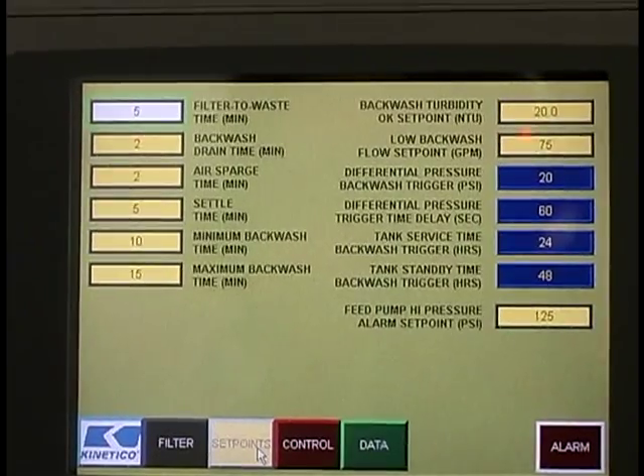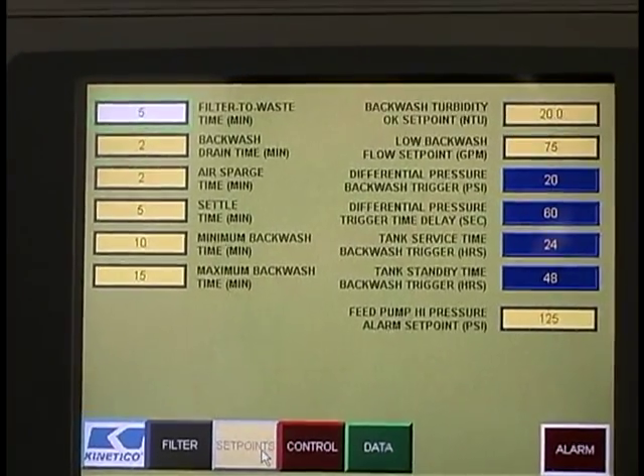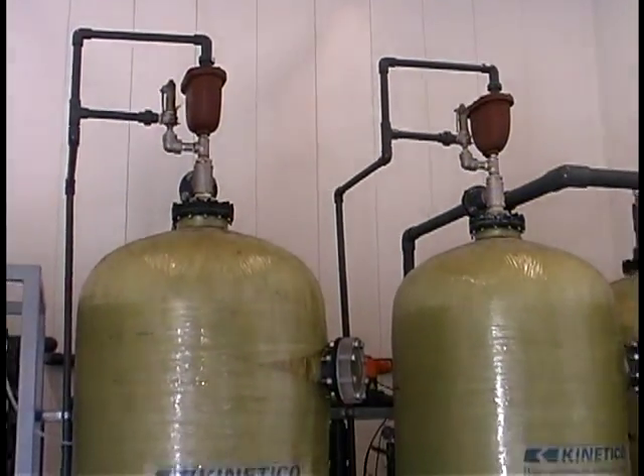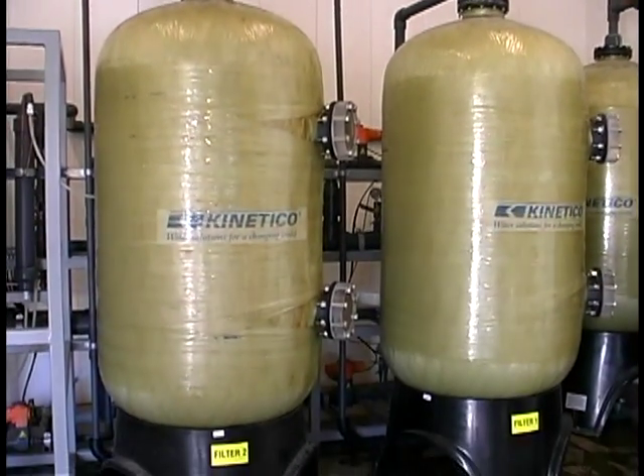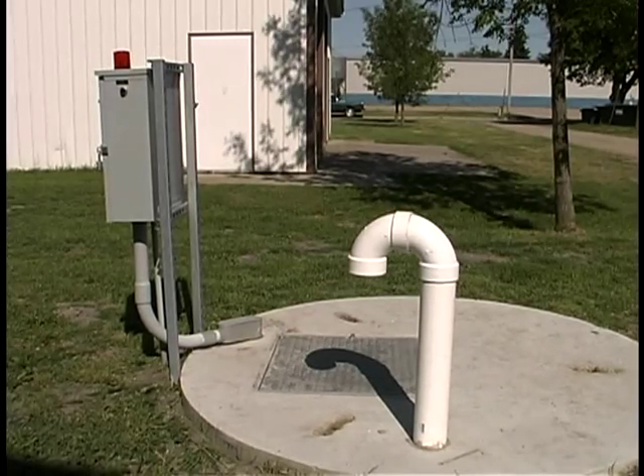The backwash includes an air sparge, brief settling, and a hydraulic wash at about 55 gallons per minute. The backwash starts by draining the tank slightly, then air sparging to stir up and dislodge material from the media grains. That settles for five minutes, then undergoes a backwash for 10 minutes. A filter-to-waste process runs for about five minutes before the filter is returned to service. Backwash is accomplished on only one filter at a time. Media lost during backwash can simply be replenished. The backwash water is discharged to the sanitary sewer via a newly constructed lift station.